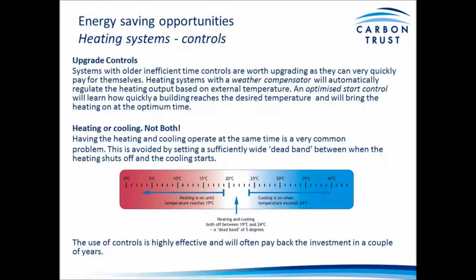A bit more detail on heating controls. Systems with older timers are generally worth upgrading. The upgrades can very quickly pay for themselves. This can often include a weather compensator that will automatically regulate heating output based on external temperatures, and an optimized start control, which will learn how quickly it takes your building to heat up to reach the desired temperatures, to start heating at the optimal time to reduce the runtime outside of operational hours.